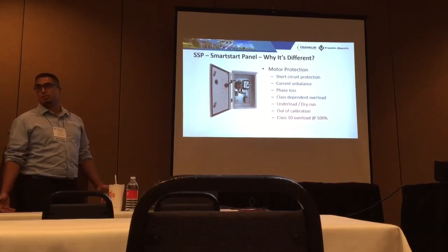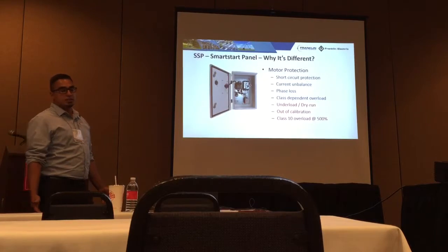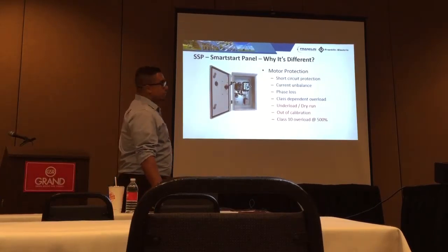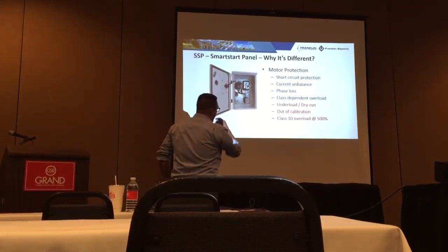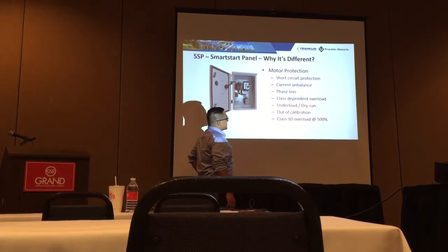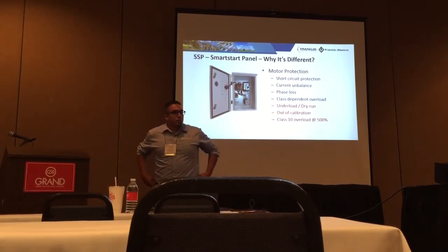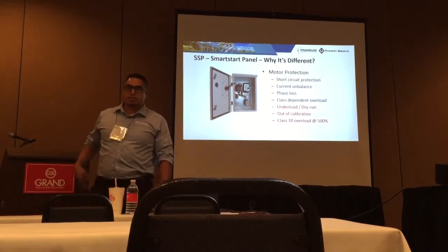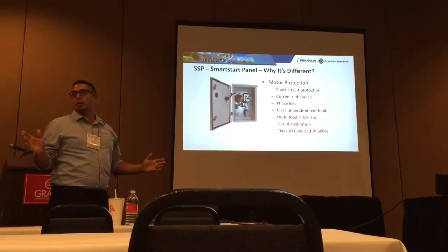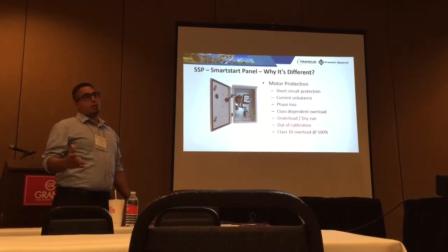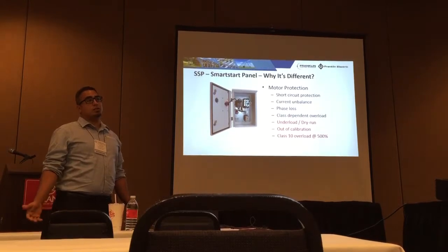tripping for a reason, the overload's tripping for a reason, what's the first thing customers do? Start turning stuff. Exactly, start turning stuff up. So the auto calibration, in another sense, think of it as a tattletale. So it kind of just defeats itself. It says something doesn't work anymore, and it gives you an auto calibration fault. Usually that's a call to you.